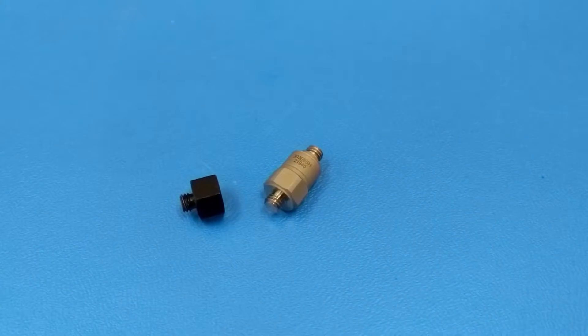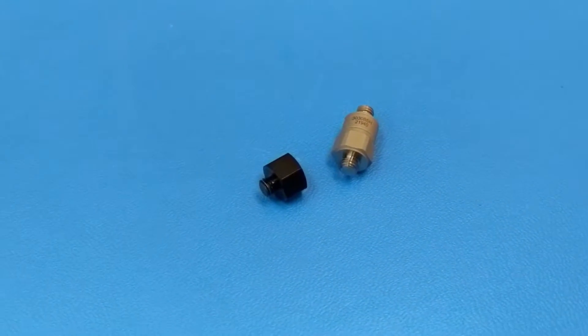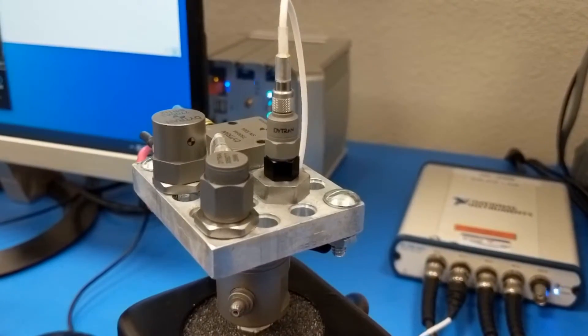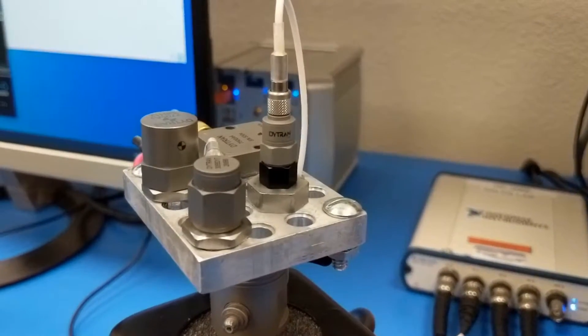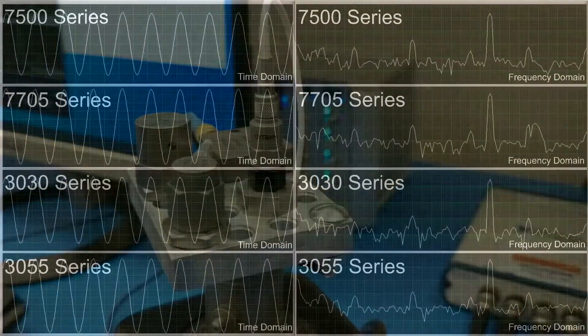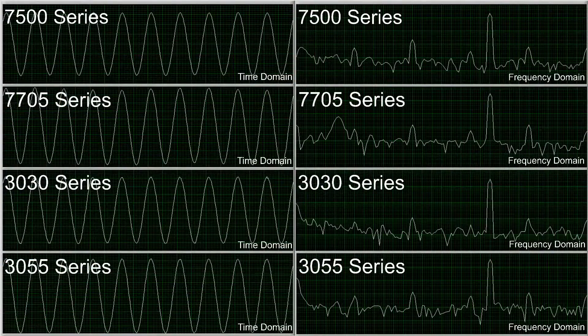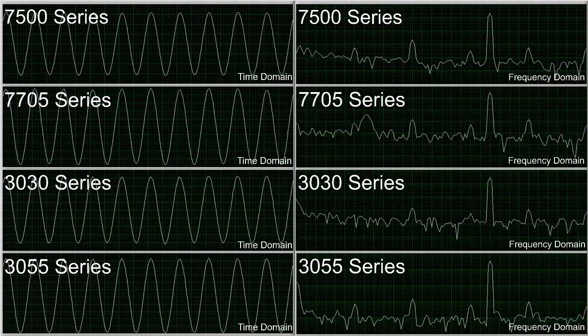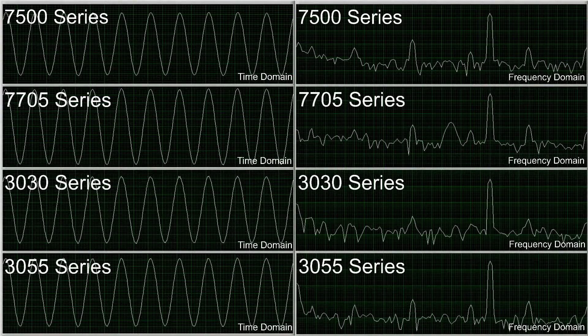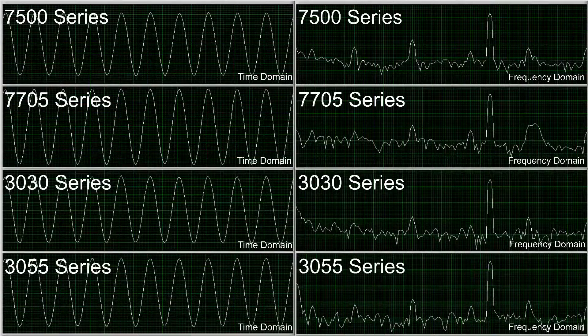DYTRAN offers a variety of isolation bases that can be used to isolate case grounded sensors from the test article. Let's install one of these bases on the 3030 series sensor and observe the effects. With the isolation base installed on the 3030 series sensor, we can no longer observe the effect of the ground loop, and we have successfully preserved the integrity of our vibration data.